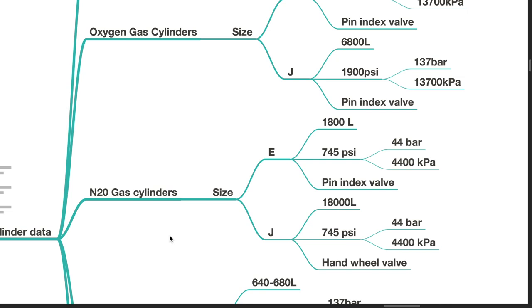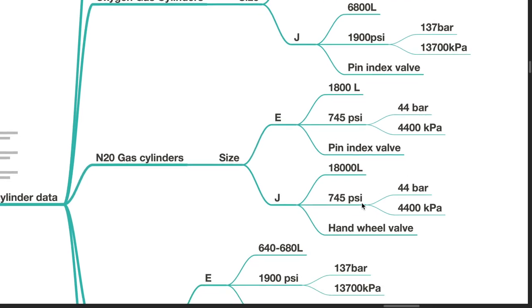Nitrous oxide gas cylinders: size E holds 1800 litres at 44 bar or 745 psi and it uses a pin index valve.